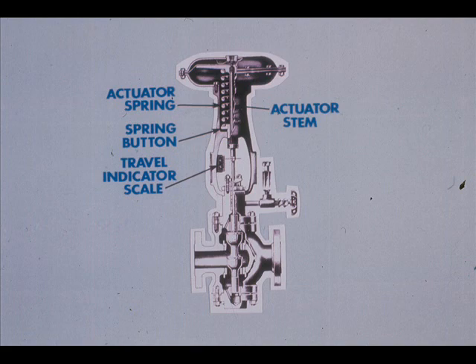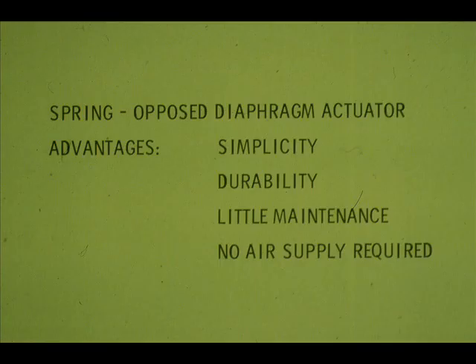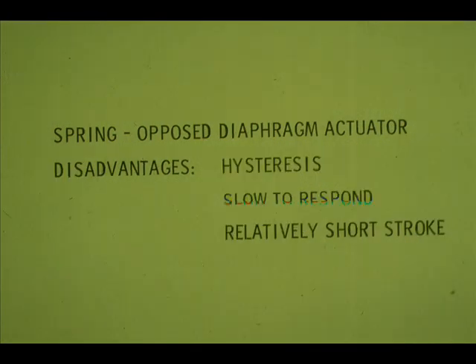Also locate the actuator stem, spring button, and travel indicator scale. The spring opposed diaphragm actuator is simple and rugged, therefore it requires little maintenance and doesn't need a constant source of air supply. However, it has some shortcomings: it has hysteresis or non-repeatability, the time it takes to travel from minimum to maximum stroke is relatively long, and its total stroke is relatively short.